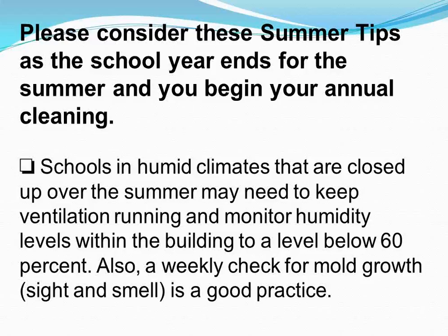Even on tile floors, you want to make sure that you get up all the moisture when you put them down. But definitely carpets. When you're cleaning carpets, if the humidity level is up around 60, I'd love to say if it's above 60, don't do it, but you'd never get anything done. So if it's really humid, if your dew point is up around 70, 72, if you can get away without doing carpets in that period of time, don't.